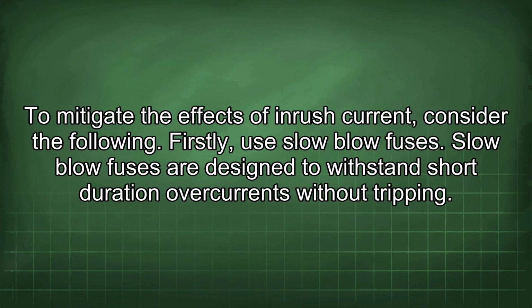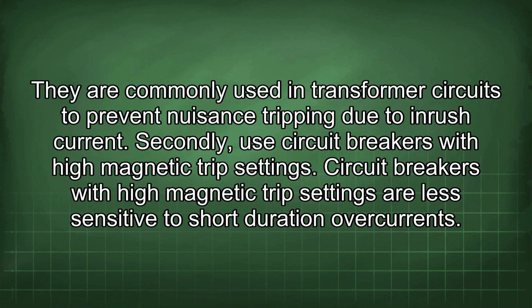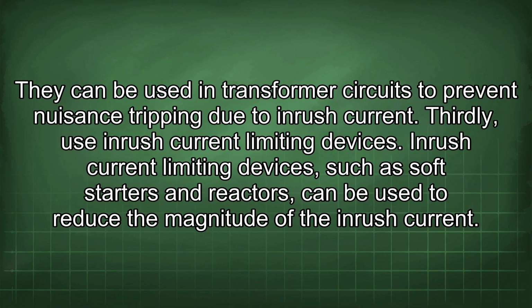To mitigate the effects of inrush current, consider the following. Firstly, use slow-blow fuses. Slow-blow fuses are designed to withstand short-duration overcurrents without tripping. They are commonly used in transformer circuits to prevent nuisance tripping due to inrush current. Secondly, use circuit breakers with high magnetic trip settings. Circuit breakers with high magnetic trip settings are less sensitive to short-duration overcurrents. They can be used in transformer circuits to prevent nuisance tripping due to inrush current.